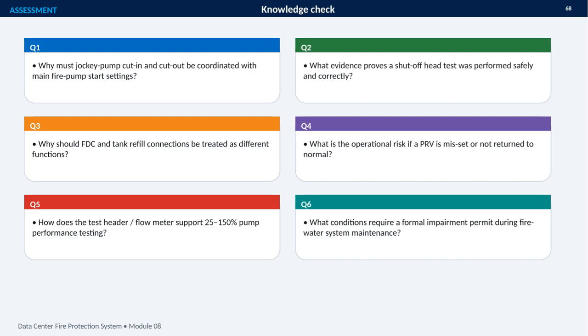Questions 3 and 4 move into system configuration and control. Be prepared to explain why fire department connections and tank refill connections serve different functions, and what could happen if a pressure-reducing valve is misset or left out of its normal position. Finally, consider how the test header or flow meter supports pump testing across the required range, from 25 to 150%, and identify the conditions that would require a formal impairment permit during maintenance. The key theme is controlled, documented, and safe operation.